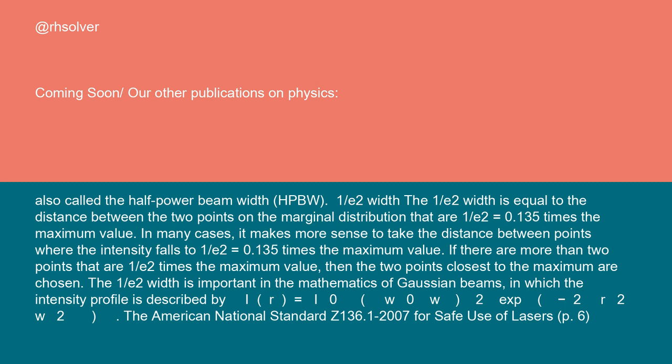The American National Standard Z136.1-2007 for safe use of lasers (page 6) defines the beam diameter as the distance between diametrically opposed points in that cross-section of a beam where the power per unit area is 1/e (0.368) times that of the peak power per unit area. This is the beam diameter definition that is used for computing the maximum permissible exposure to a laser beam. In addition, the Federal Aviation Administration also uses the 1/e definition for laser safety calculations in FAA Order JO 7400.2 paragraph 29-1-5D.